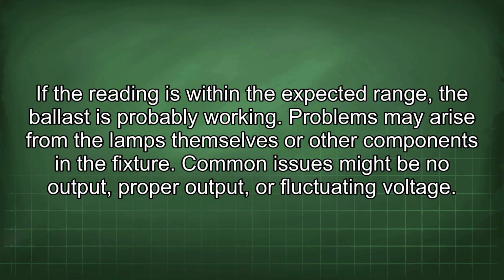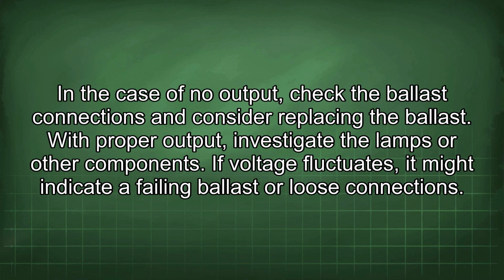Problems may arise from the lamps themselves or other components in the fixture. Common issues might be no output, proper output, or fluctuating voltage. In the case of no output, check the ballast connections and consider replacing the ballast. With proper output, investigate the lamps or other components. If voltage fluctuates, it might indicate a failing ballast or loose connections.